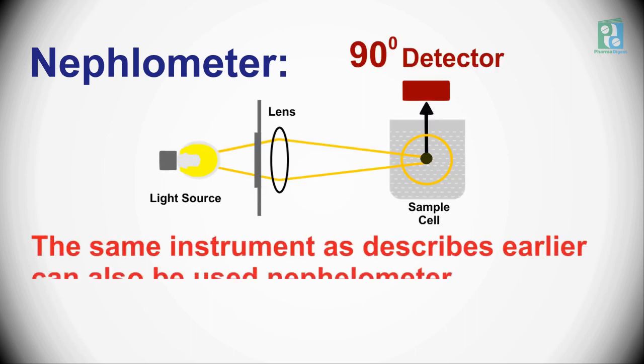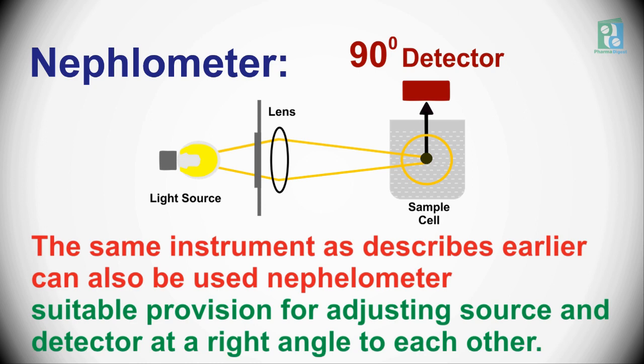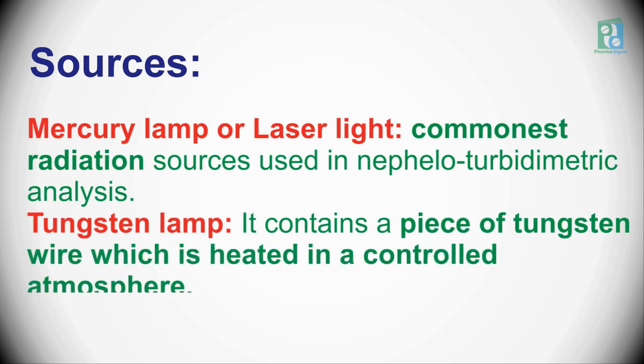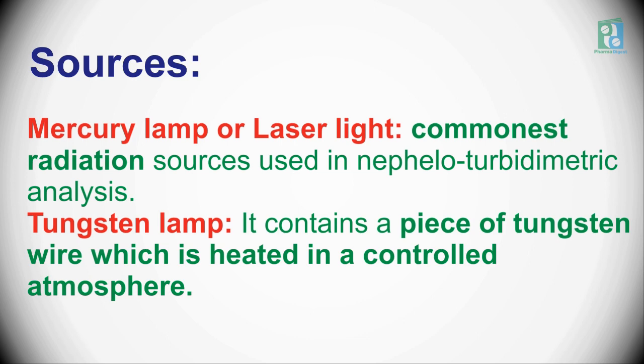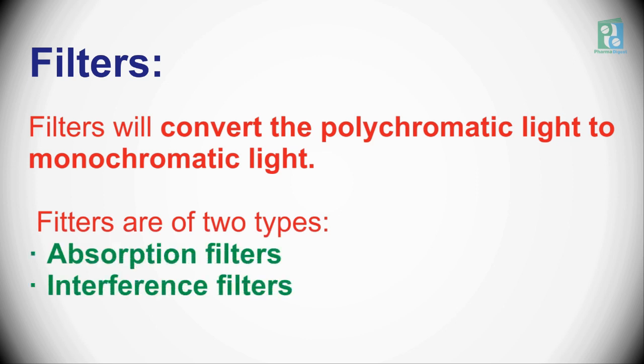In a Nephelometer, the same instrument as described above can also be used. However, in this case the instrument should have a suitable provision for adjusting the source and detector at a right angle to each other. Mercury arc lamp or laser light are some of the commonest radiation sources used in Nephelometer analysis. Tungsten lamp, which contains a piece of tungsten wire heated in a controlled atmosphere, is also used. The filters will convert polychromatic light to monochromatic light, and generally filters are used for this purpose.